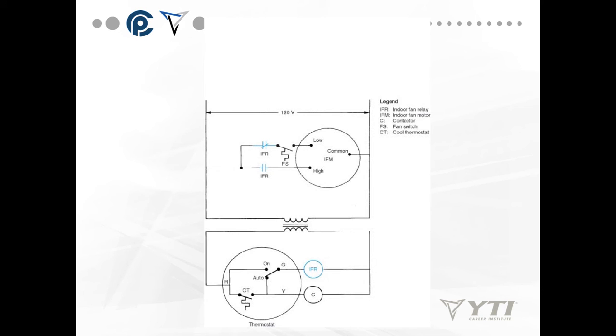Okay, this is a schematic diagram with a transformer in the diagram. It's actually a fan diagram that you'll probably see in the air handler. So here we have our transformer. Our primary side is the side with 120 volts on it. Here we have our transformer again with 24 volts coming off the secondary side going to R on the thermostat. Coming out of Y on the thermostat, which is our cooling part of the thermostat, we have a contactor coil. Coming out of that, we return to common.